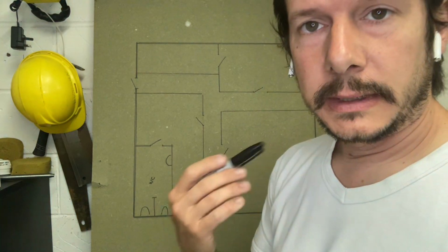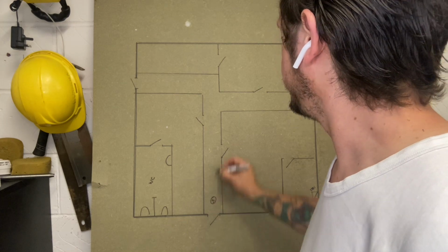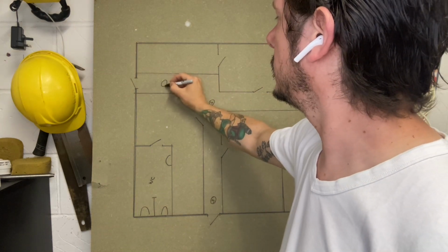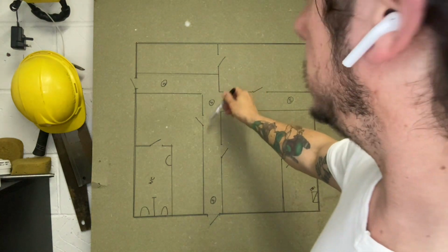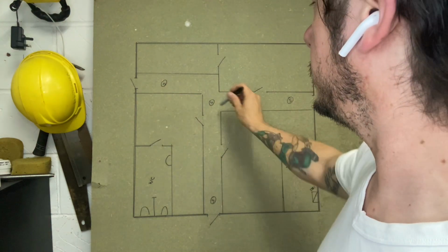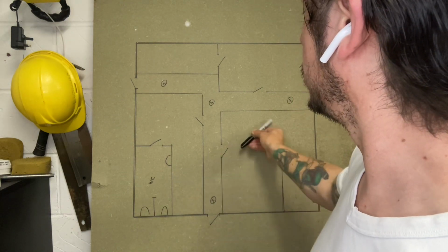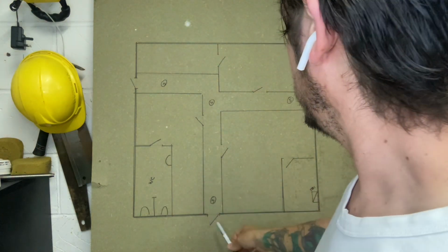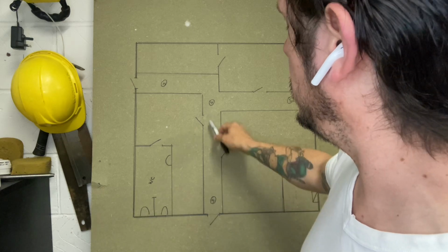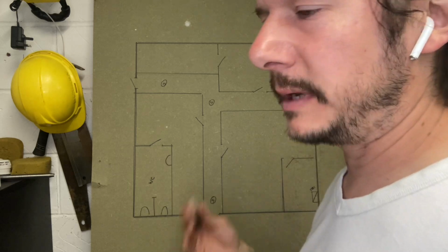Right, L4, escape routes. So we're going to be covering with smoke detectors. We put smoke detectors on escape routes, wherever we need them. Be wary of flow of air. Depending on the length and the width, this detector here might cover the whole distance theoretically, but smoke might get pulled into these other rooms if they've got windows. I've drawn windows in, it's the gulag, but smoke could get pulled around. So you've got to be wary of where the smoke's going to go. In essence, we're dealing with the study of how air moves.